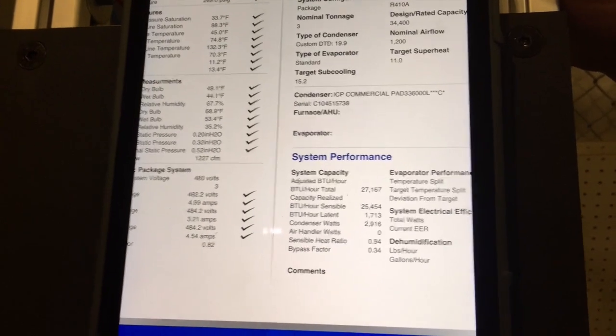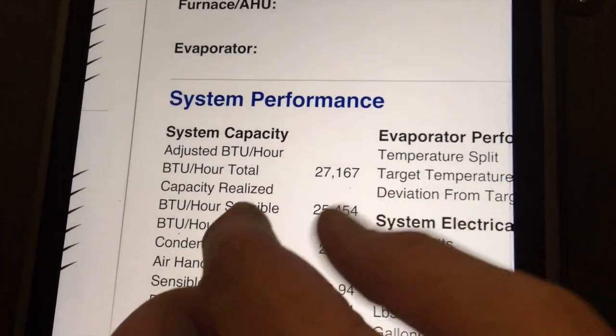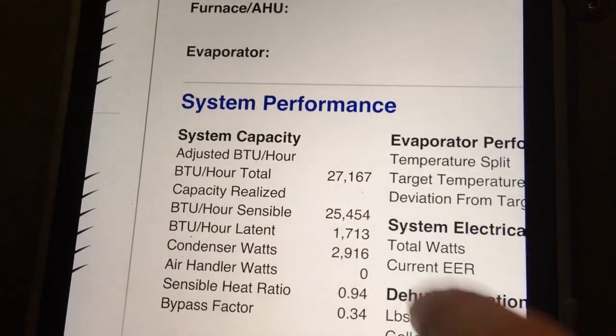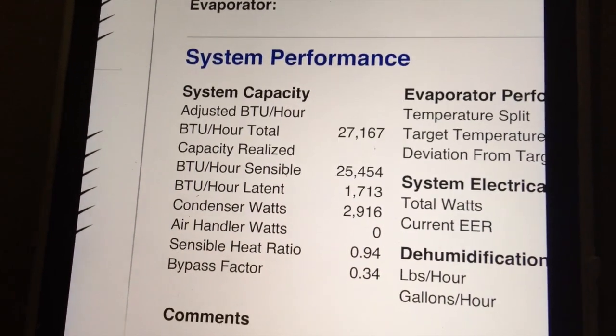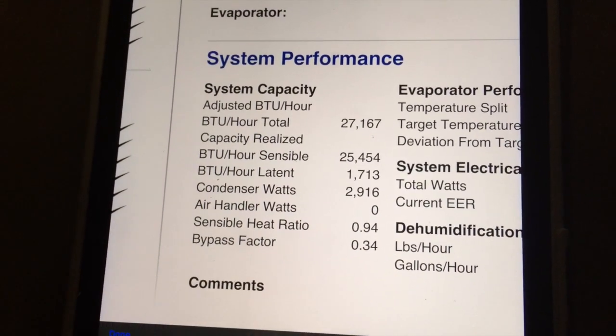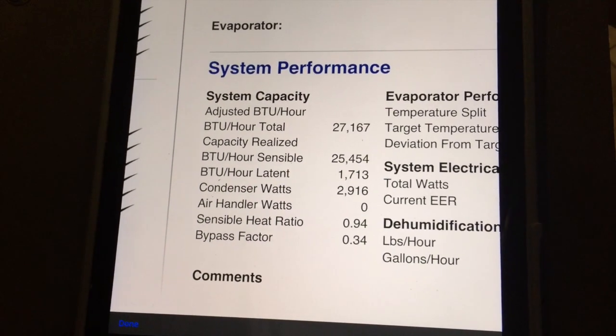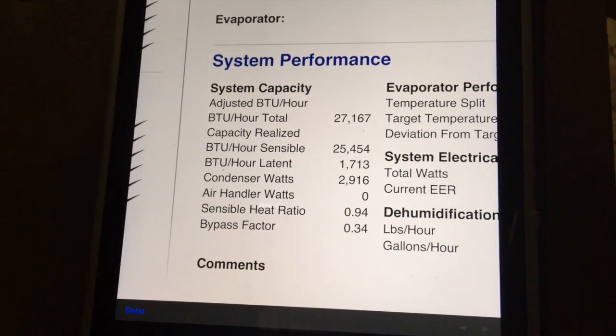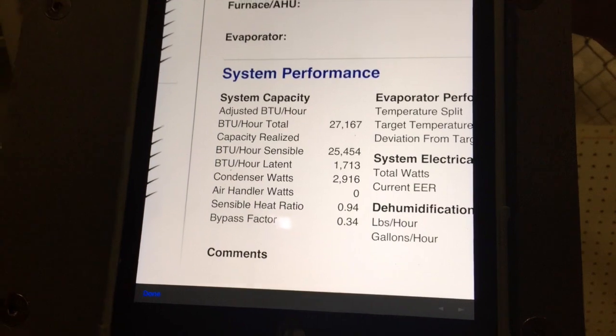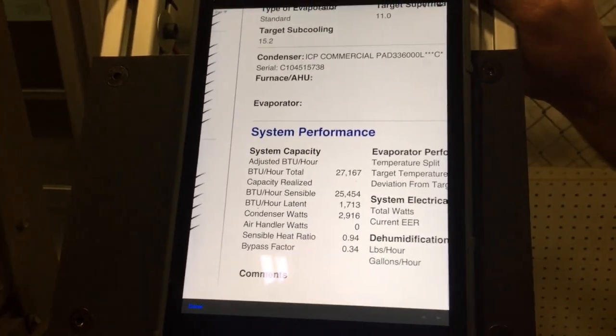Now, there are two readings here. You'll notice that we don't have adjusted capacity and adjusted and realized capacity. The reason that those aren't showing up in this case is because our temperature is 68 degrees. We're below the threshold where those things can be calculated by the application, and that's just part of physics. It's not a limitation of our tool, but actually a limitation of physics, that you cannot look at air conditioning performance below about 70 degrees. It just is impossible.